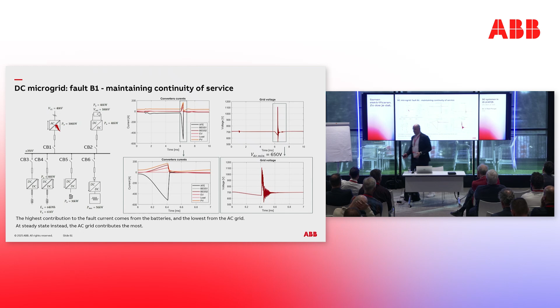And here we see the simulated operation of the solid-state circuit breaker. This is the overall simulation. Here is the current. You can see the rise. It was tripped at 500 ampere. And then after tripping, there is some overvoltage happening. This is essentially because we still have some energy in the system, and that is going to oscillate.